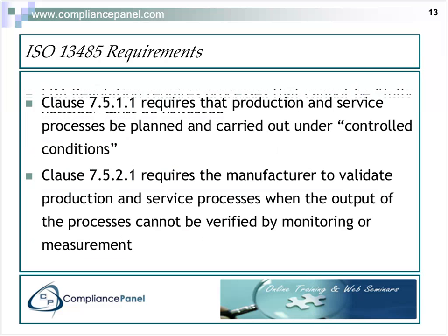Okay, I mentioned that we have other requirements beside FDA. If we look at ISO 13485, which of course is the quality system requirement for many other countries in the world, in Japan that is part of the regulation. It has been translated into law. In Europe, of course, there's a harmonized standard there, and if you choose to use it, you must comply with that harmonized standard.